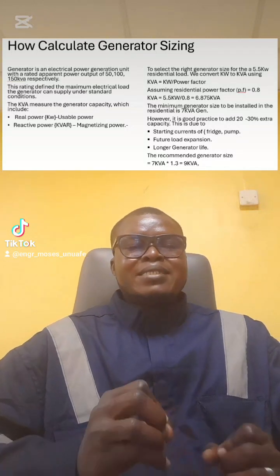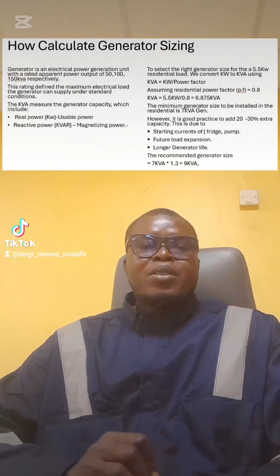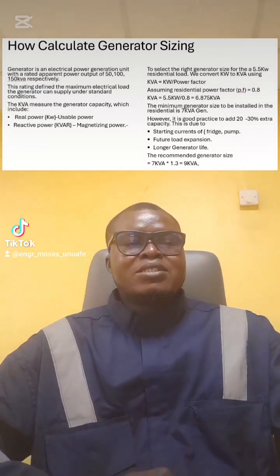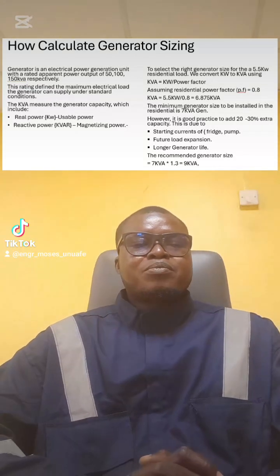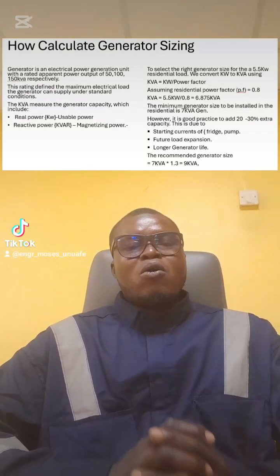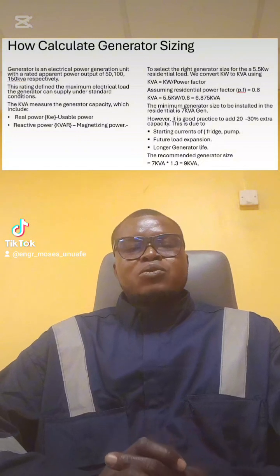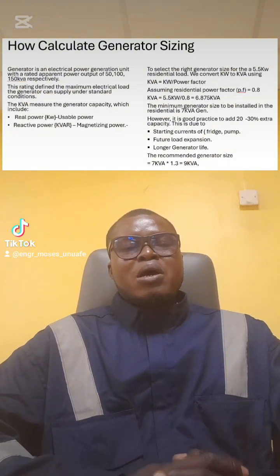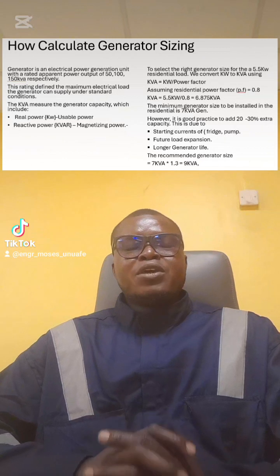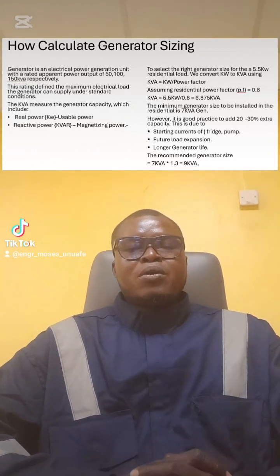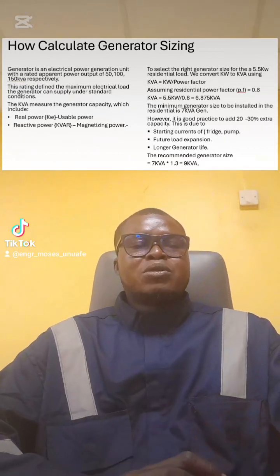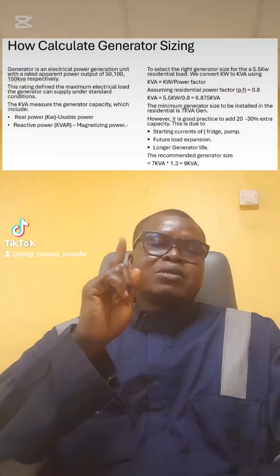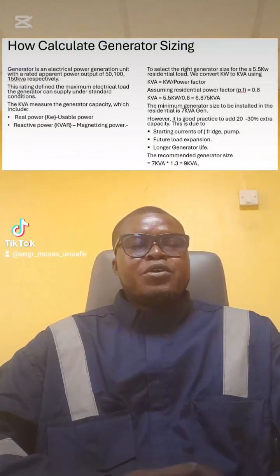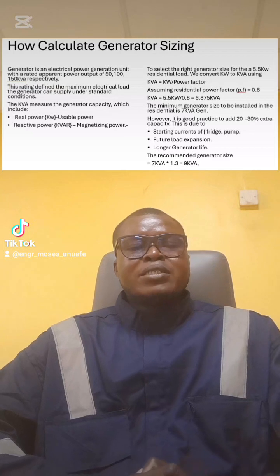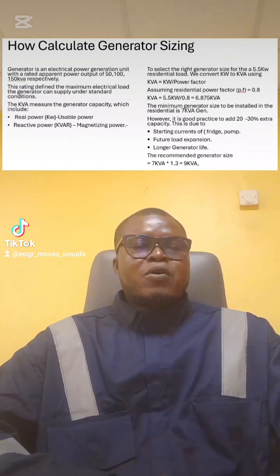Now, in selecting the right generator size for this residential load, we have to first convert the kilowatts, which is the residential load that we have measured, to kVA. By so doing, we are going to substitute it into the formula, as you can see above. kVA equals kilowatts divided by the power factor.